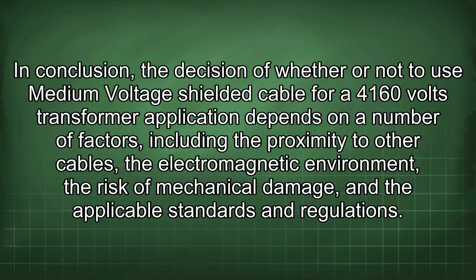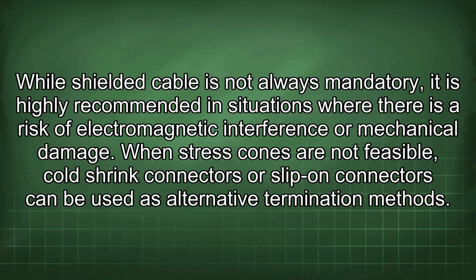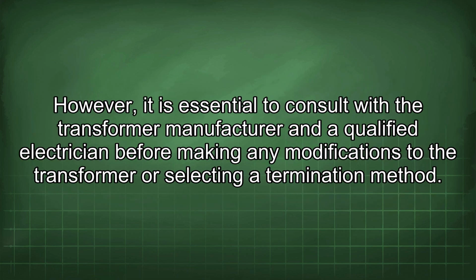In conclusion, the decision of whether or not to use medium-voltage shielded cable for a 4160 volts transformer application depends on a number of factors, including the proximity to other cables, the electromagnetic environment, the risk of mechanical damage, and the applicable standards and regulations. While shielded cable is not always mandatory, it is highly recommended in situations where there is a risk of electromagnetic interference or mechanical damage. When stress cones are not feasible, cold shrink connectors or slip-on connectors can be used as alternative termination methods. However, it is essential to consult with the transformer manufacturer and a qualified electrician before making any modifications to the transformer or selecting a termination method.